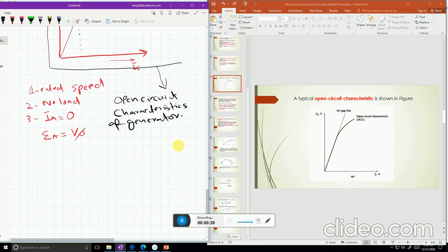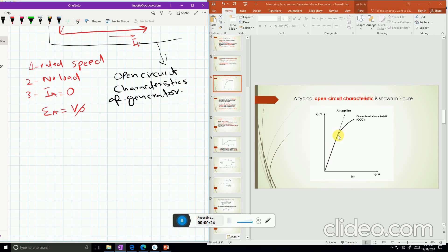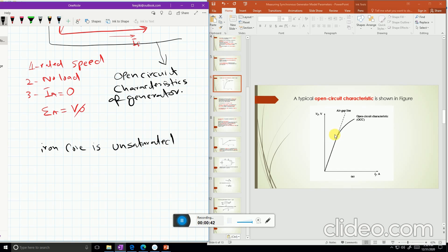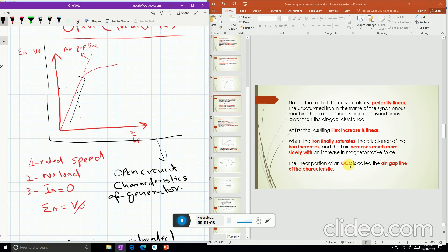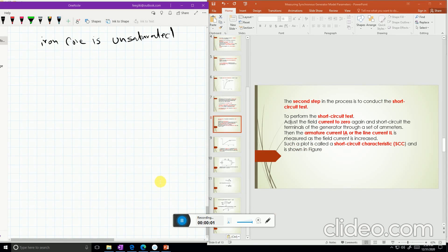In the open circuit characteristics, the beginning of the line is linear, but at higher values it becomes nonlinear. The reason is that initially the iron core is unsaturated, but as field current increases the flux in the iron core increases until saturation begins, so the increase in field current no longer increases V-phase linearly. The linear portion of the open circuit characteristics is called the air gap line.